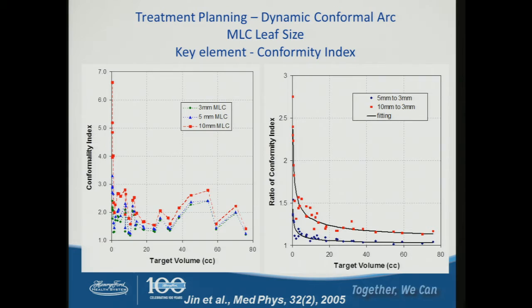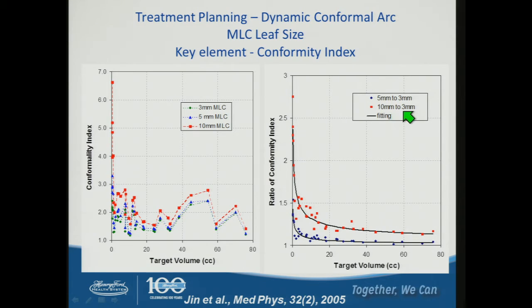Regarding MLC leaf size: nobody really uses 1 cm leaf size anymore, but many clinics still have 5 mm. We evaluated conformality index versus target volume for different leaf sizes (3, 5, and 10 mm). For very small lesions, conformality index increases significantly with 5 mm leaves. If the lesion is less than about 5 cc, you may not be able to treat on a regular LINAC with 5 mm leaf size, but high-definition leaves may work. This gives you guidance on what patients can be treated on your regular LINAC.